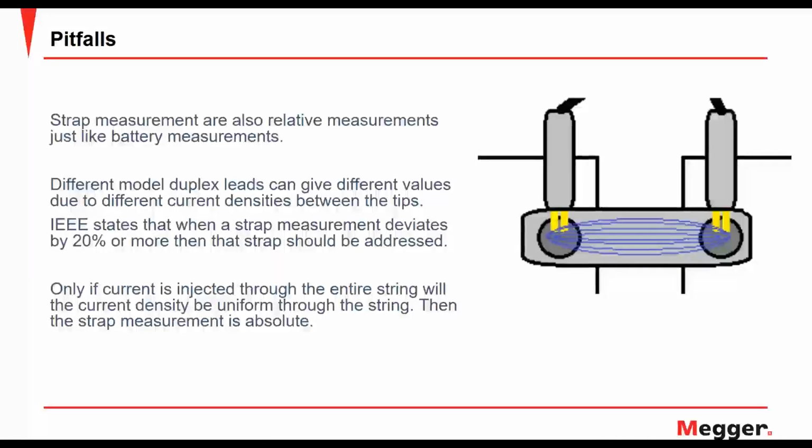It takes time for this current to be distributed to give you a very stable reading. So when I'm doing this with different probes, having a different mechanical or physical shape from the previous one, I might get a different reading. So on this, I might indicate that maybe there is a problem in there.